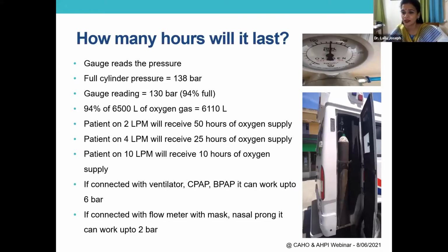The full gauge pressure for a D-type cylinder is about 138 bar. Now, in this particular example, it's about 130 bar, which means the cylinder is about 94% full. So when it is about 94% full of 6,500 liters, it means you have 6,110 liters. So if your patient is on 2 liters per minute, you can transfer him from probably Kanyakumari to Kashmir. 50 hours of oxygen supply will be there. If he's on 4 liters, then it is about 25 hours; at 10 liters, about 10 hours.